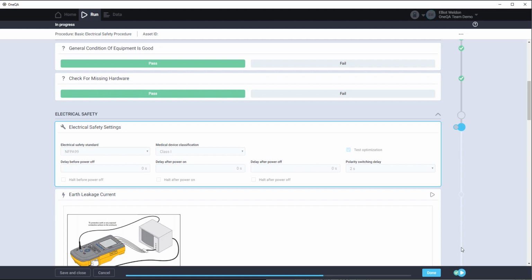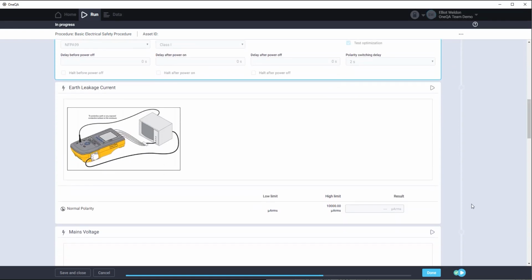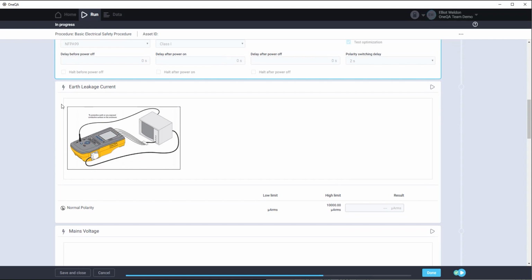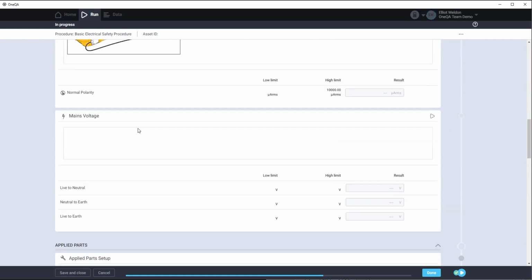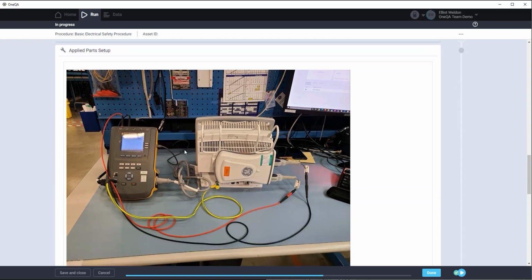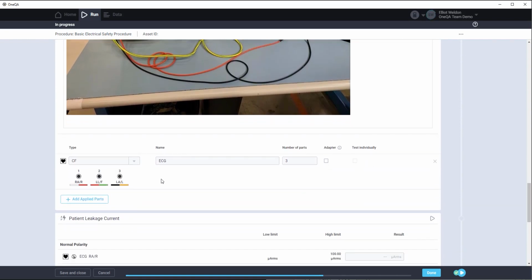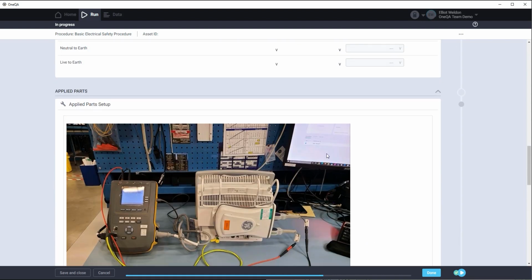Now keep in mind, we're still going to have to connect our Fluke devices to the device under test, so we can add diagrams and pictures into the test. Here we have our applied part set up. We only have a 3-lead ECG on this device that we're testing today, but let's just say that you had more than 5 applied parts, meaning maybe 5 ECG leads and an SpO2 sensor. We can use Fluke Biomedical's 1-to-10 adapter that will allow us to do these tests also with OneQA.